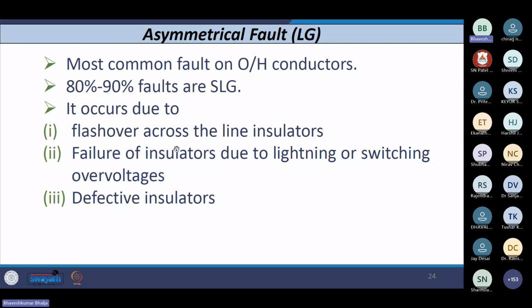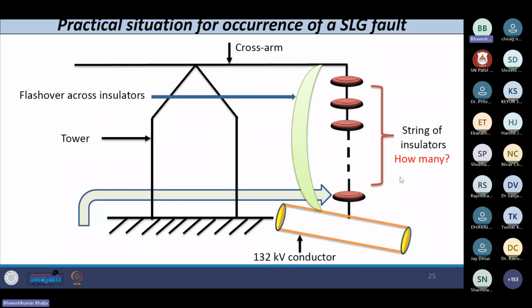Most line to ground faults occur because of flashover across the line insulators. In the figure, I have shown a string of insulators, where each disc is rated 11 kV, and you can calculate the number depending upon the voltage level used. Let's say 132 kV: you divide 132 kV by root 3, because the string is connected between the live conductor and the cross arm, which is at ground level, and then divide by the rating of each insulator, 11 kV. Based on that, you can calculate how many insulators are required.